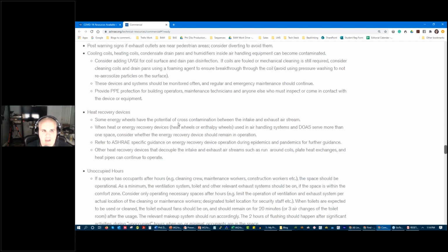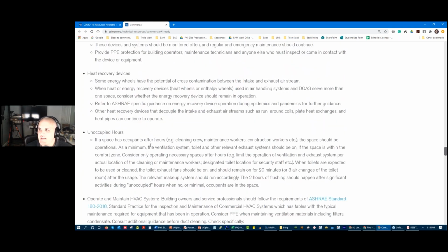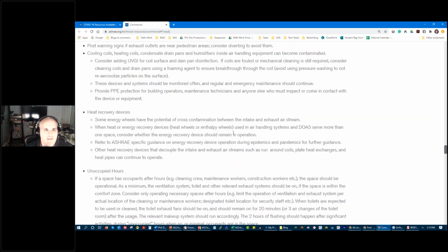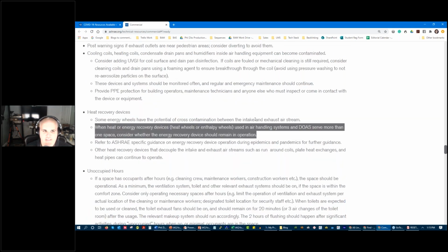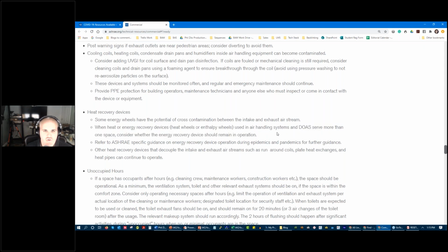It talks about different strategies based on system types. I didn't discuss desiccant wheels, but enthalpy wheels, also known as desiccant wheels, and heat wheels, things that expose themselves to the return stream and then re-expose themselves to the incoming supply stream, they want those disabled. Oh, wait, no. They don't want them disabled anymore. See, this is why you've got to read it repeatedly. They changed it. It used to say that you wanted these wheels disabled. Now it says that you should keep them in operation. Well, consider whether you keep them in operation. All right.